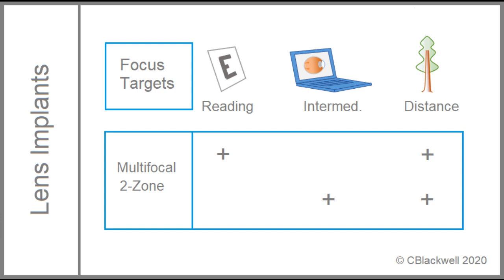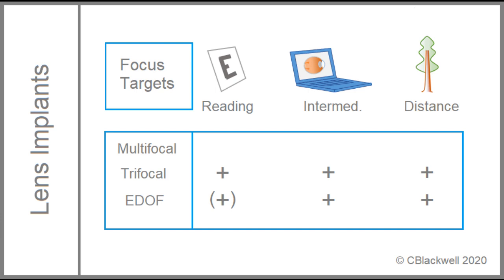The single power lens implant with one focal distance has its advantages: it gives a high level of image quality, has good performance in low light because the entire lens is gathering light, and it is the least expensive. Moving on to multifocal lenses — early versions had two focal distances. One version had its foci set at far and near; the other at far and intermediate. Each had a missing distance, so it became an option to mix them using one lens of each type. The current generation of multifocal lenses aims to improve functionality at all three distances. The trifocal lens divides light into three different focal points, whereas an extended depth of focus lens — EDOF for short — aims to broaden the depth of focus. Both seem to be working well, with the trifocal having an advantage at near.